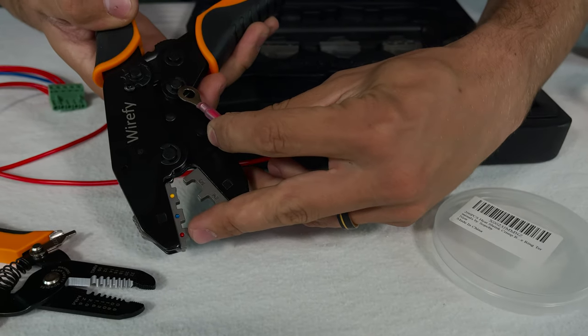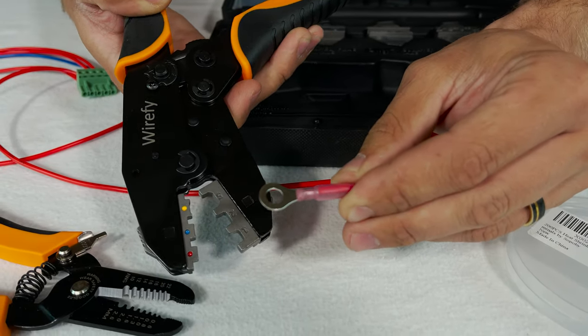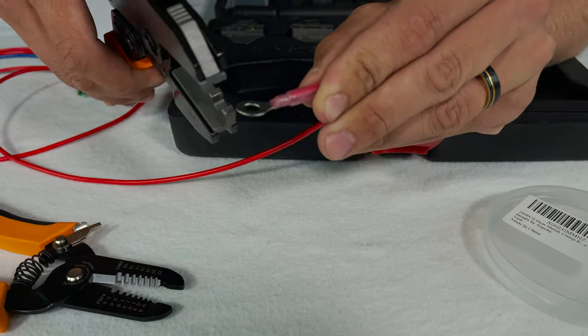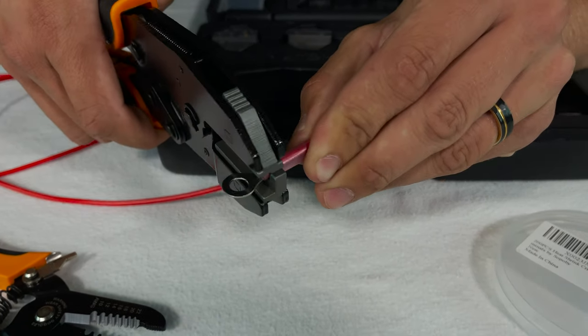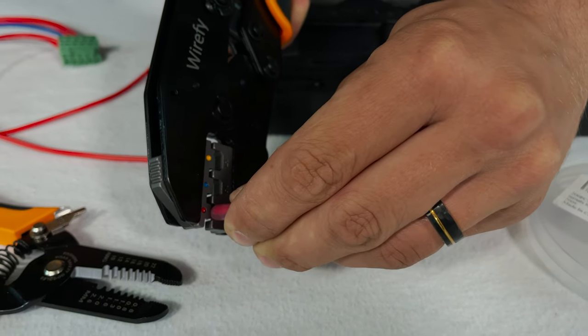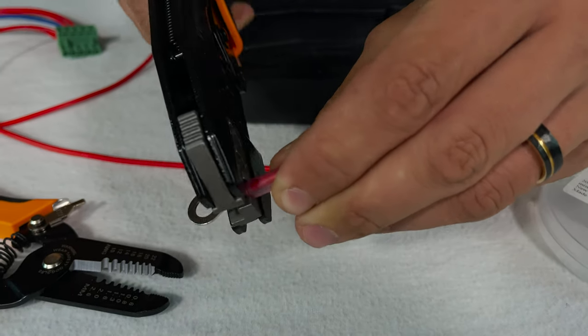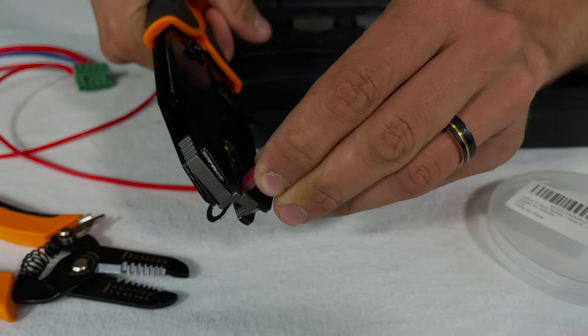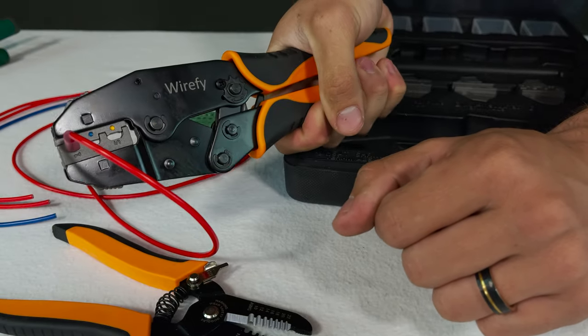And I'm gonna put it on the red setting here because this is a red connector and the color codes are based on the wire size. And I'm gonna get it on there like that as you can see and then squeeze this all the way down and I'm gonna go until the handles touch together.